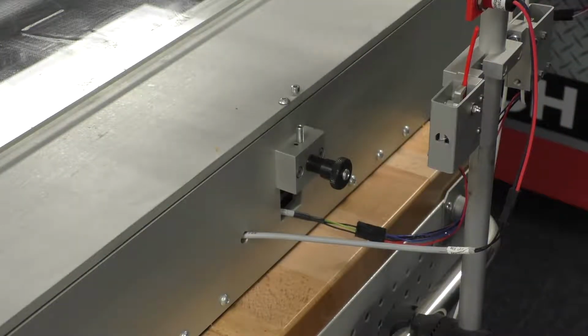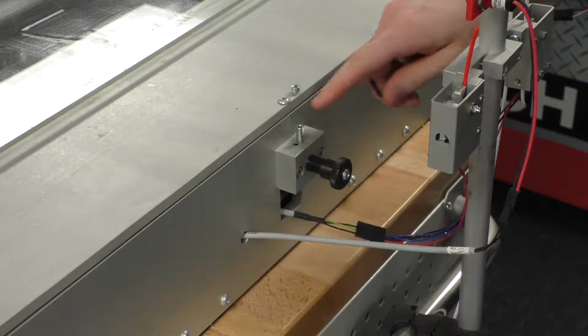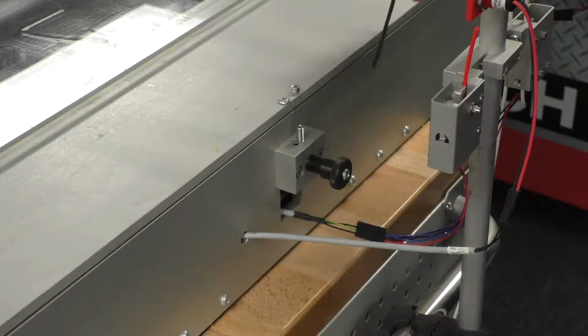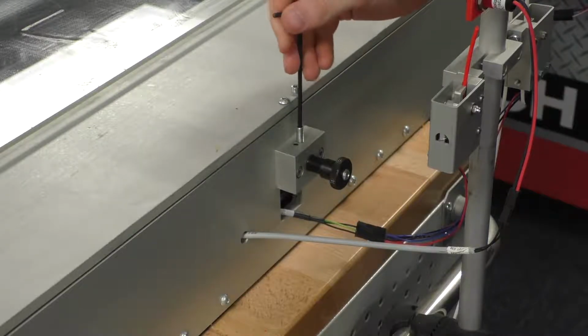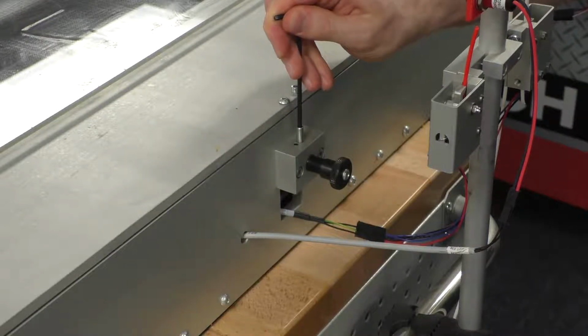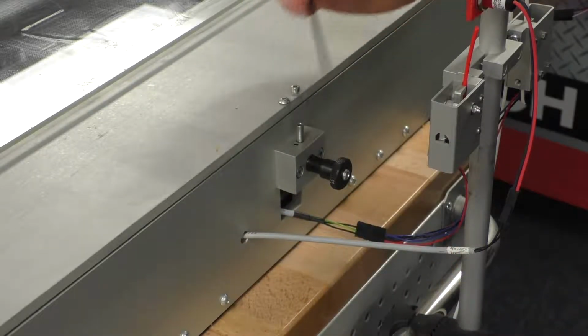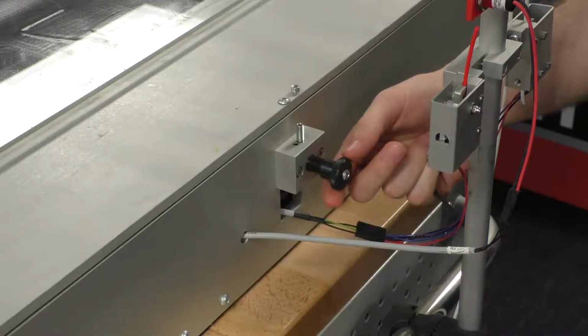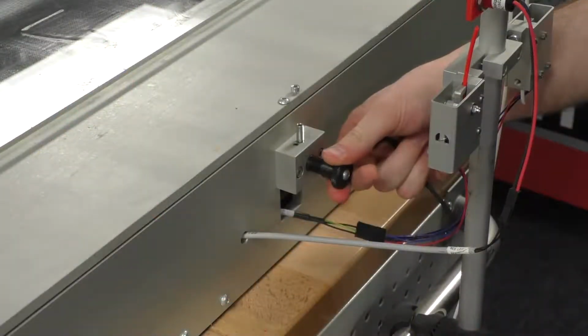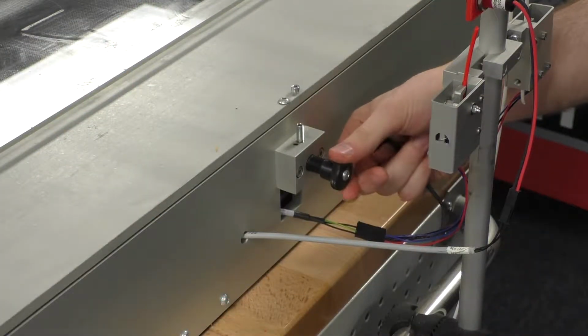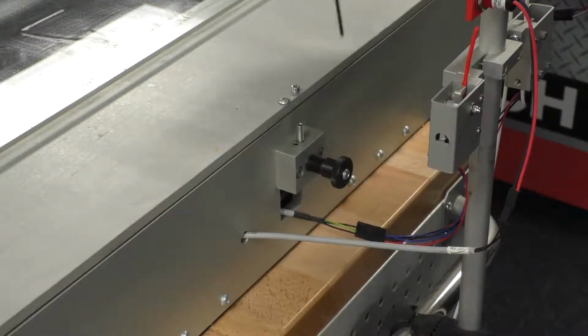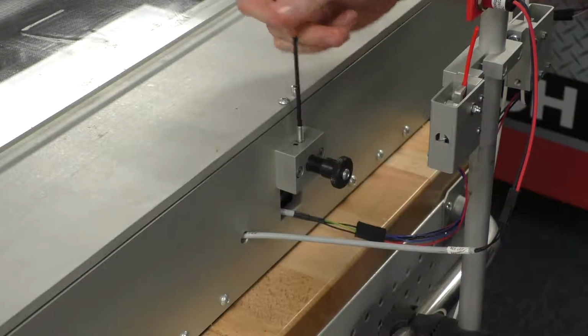The adjustment for the center pin is slightly different. We adjust that from the back of the machine. We've got a set screw and a knob. So to adjust the center pin, we're going to back off the set screw to allow adjustment. Once that's loose, we're going to turn the knob. We're going to turn the knob counterclockwise to raise the center pin. And we're going to turn the knob clockwise to lower the center pin. Once we're done setting the center pin, we're going to retighten the set screw to lock it in place.